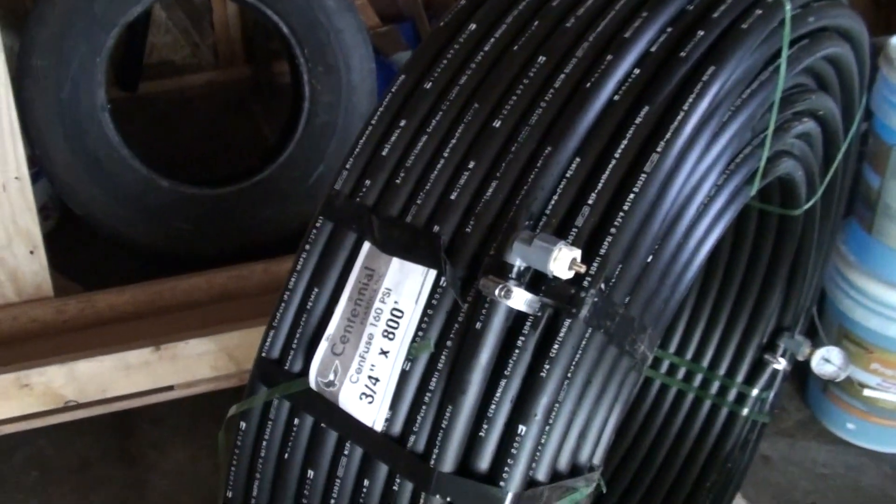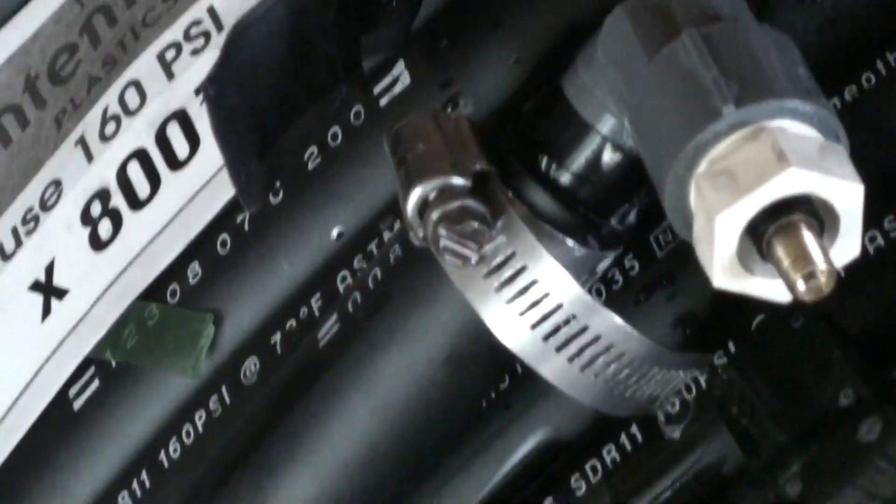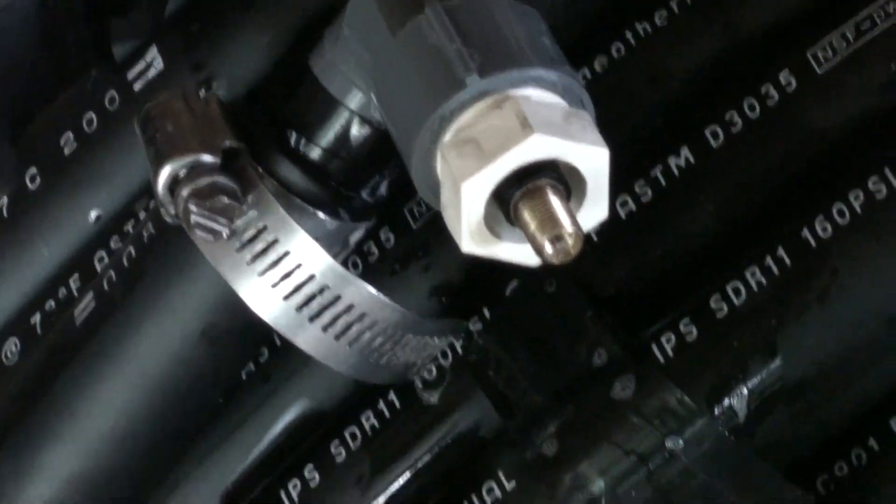This is my way of testing. This roll of tubing had some nicks on it from the pallet where it was laying when it shipped, and I was a little concerned that they might be deep enough to leak. So I needed a tester before I bury this in the ground, so I made a tester.